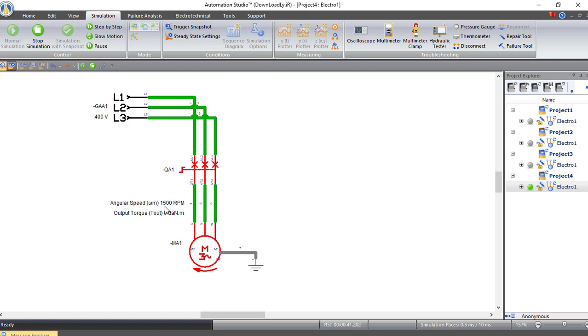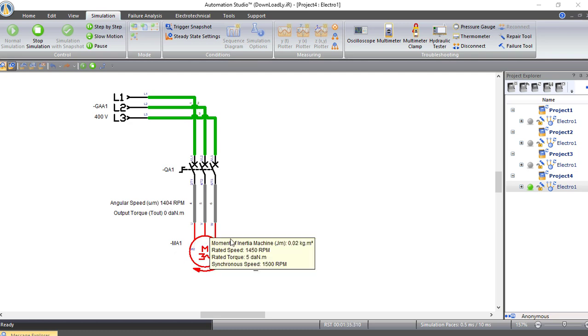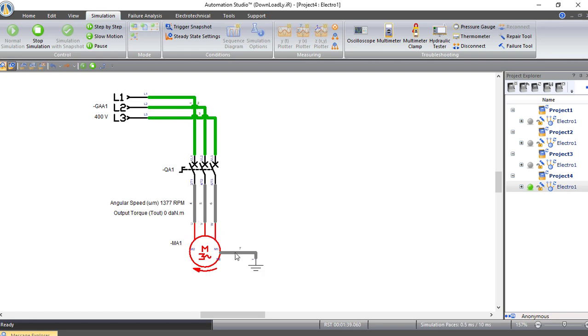Of course, in an induction motor there is no exact 1500 RPM — there will be some slip, resulting in approximately 1450 RPM. Now the motor is rotating clockwise. When we open the circuit again, the motor will stop but it continues rotating due to inertia — it has stored mechanical energy and will keep rotating until inertia reaches zero. Electrically there is no power supplying the motor, but when we close the circuit again, the speed increases back to maximum.